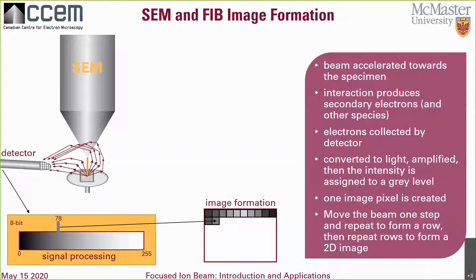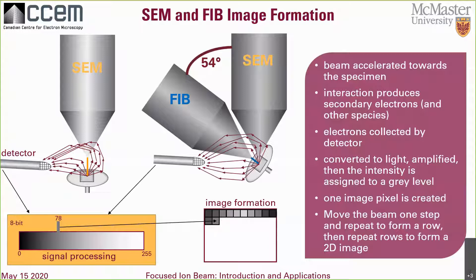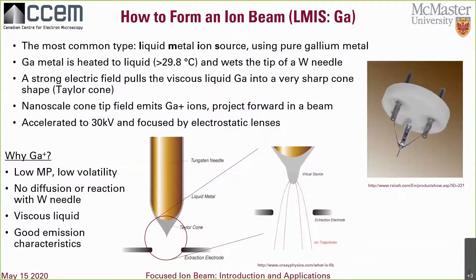Instead of an electron beam, we can do this exact same thing with the ion beam. Secondary electrons will be induced by the ion beam interaction with the material and they can be collected to form an image. Here's how an ion beam works, specifically the gallium kind used most often in FIB. Gallium metal is heated to liquid and wets the tip of a tungsten needle where a strong electric field pulls the liquid gallium into a very sharp cone tip. The tip acts as a field emitter so gallium ions are ionized and projected forward in a beam, accelerated to typically 30 kV and focused by electrostatic lenses.